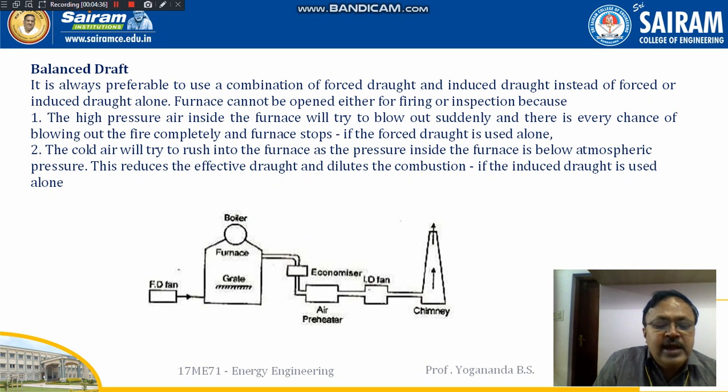Balanced draft is the combination of the forced draft and the induced draft. Here we have the forced draft fan situated near the boiler, whereas the induced draft fan is situated near the chimney. The high pressure air inside the furnace will try to blow out suddenly, so there is every chance of blowing out the fire completely and the furnace stopping functioning if you use forced draft alone.